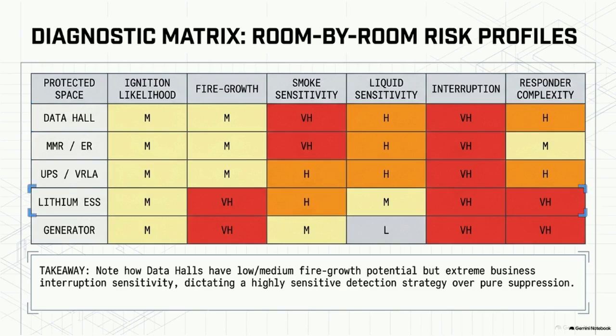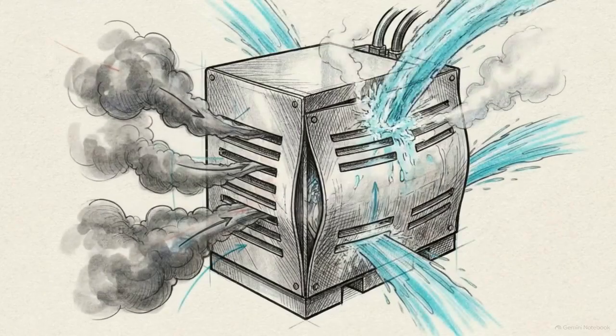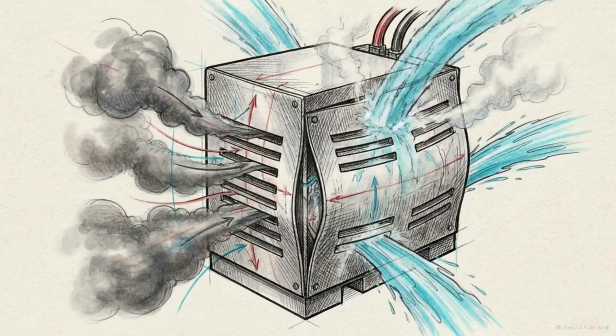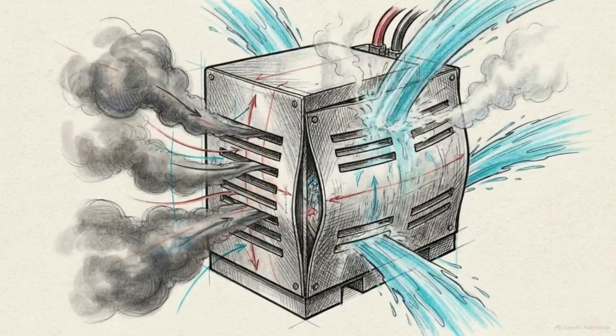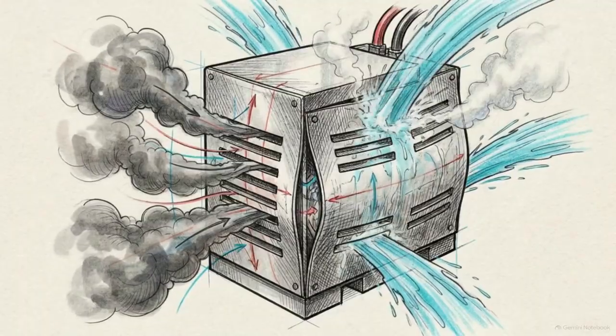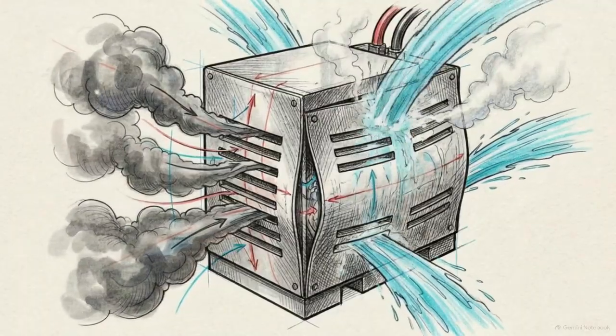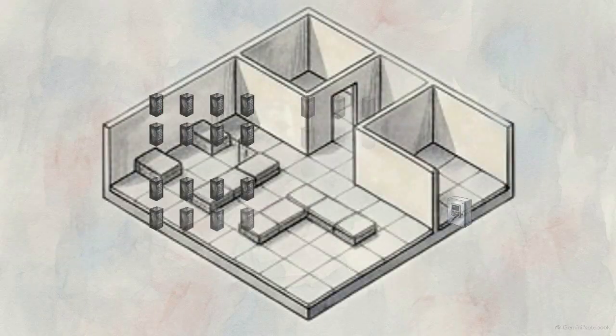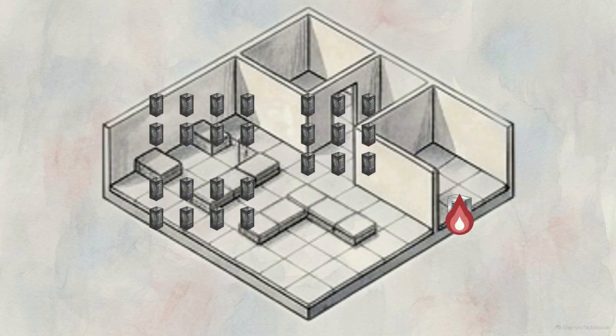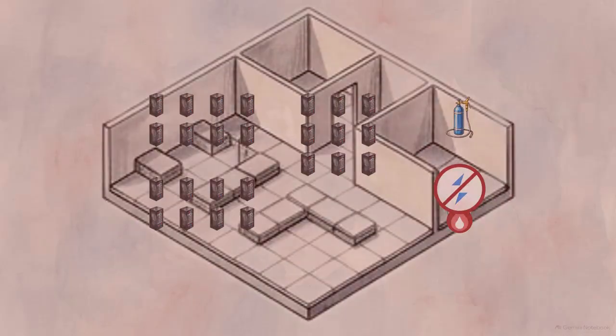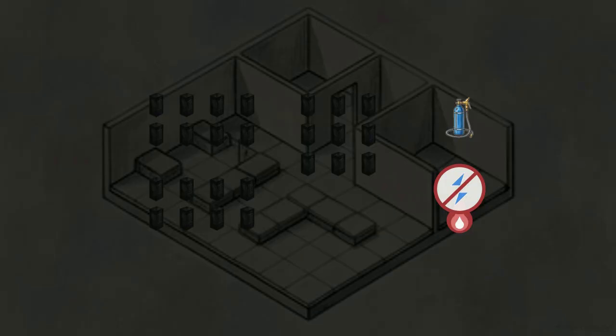Contrast that with the row for a lithium-ion energy storage system. The primary ESS risk is thermal runaway, resulting in toxic deflagration. Managing this event requires active exposure cooling and dedicated venting to prevent structural spread. Applying the wrong mitigative barrier to a specialized room can trigger a cascading facility outage rather than containing the fire.